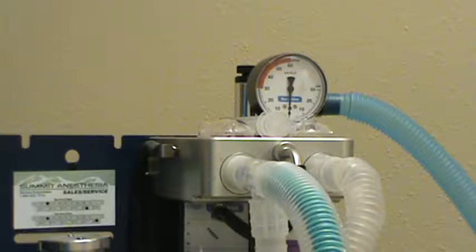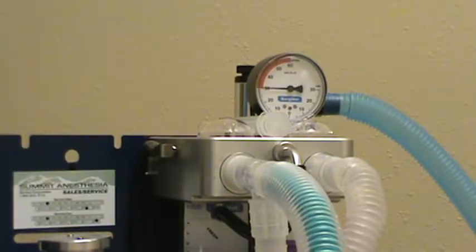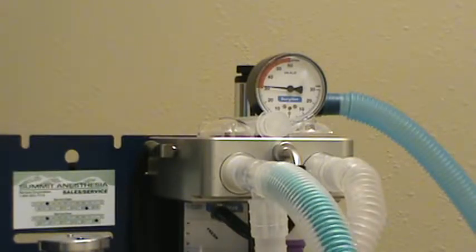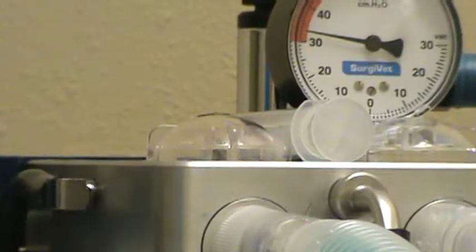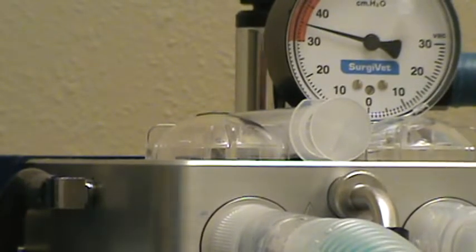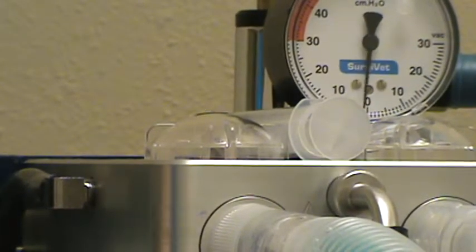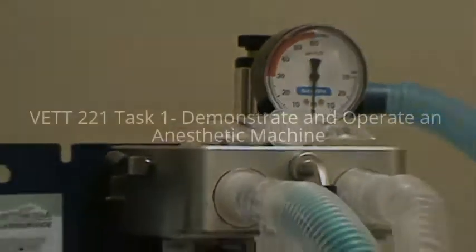We're zoomed in there and it looks like it's holding at 30. If anything, it's going up. That's good. You don't want to see that falling. Now we're going to release the pressure pop-off valve and that worked correctly. We're going to get rid of that oxygen into the scavenging system.